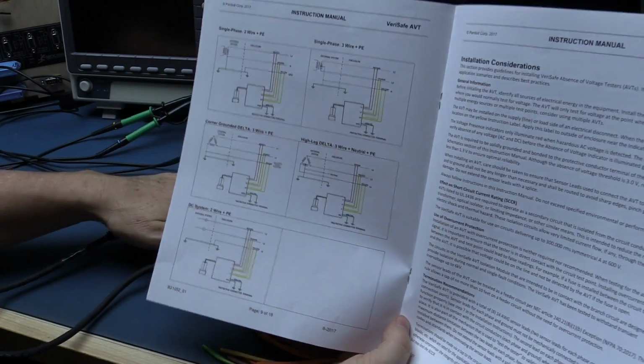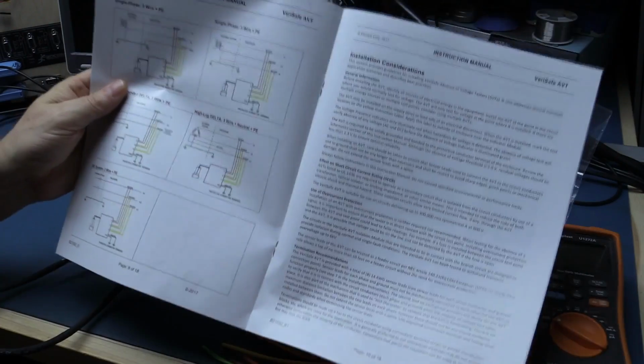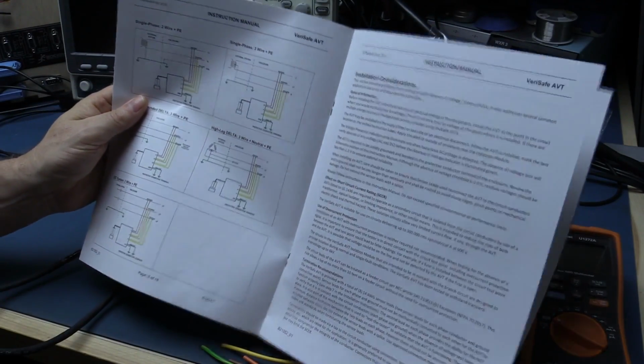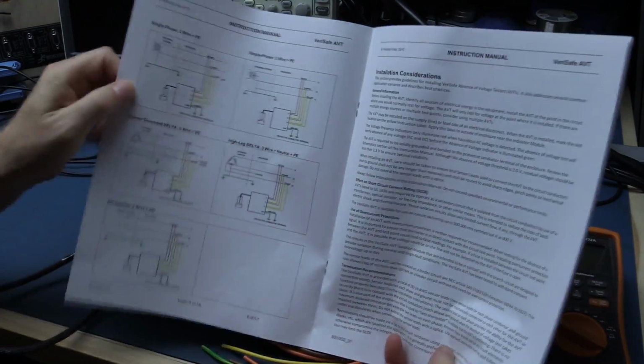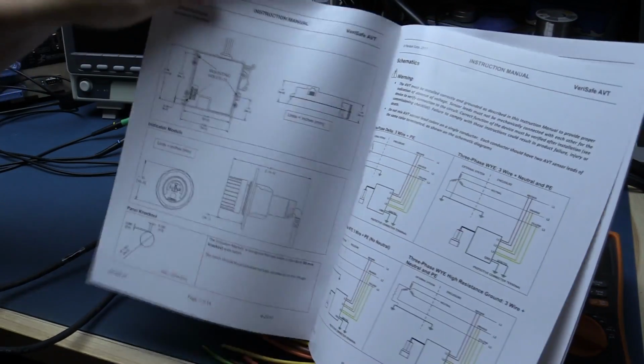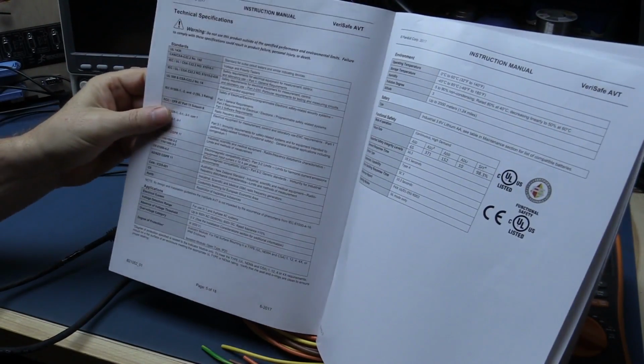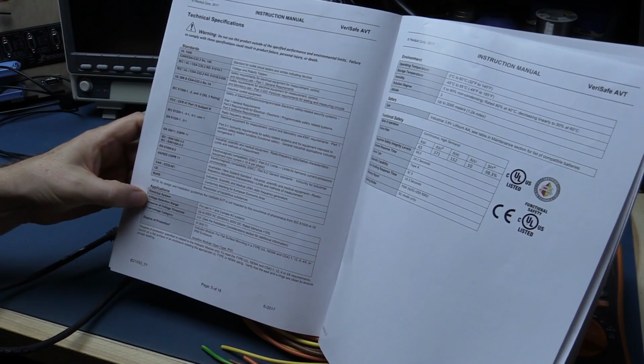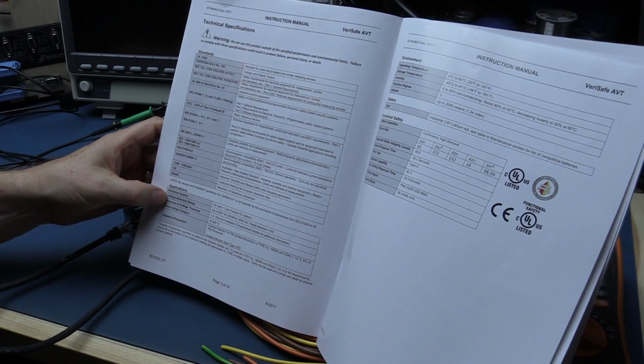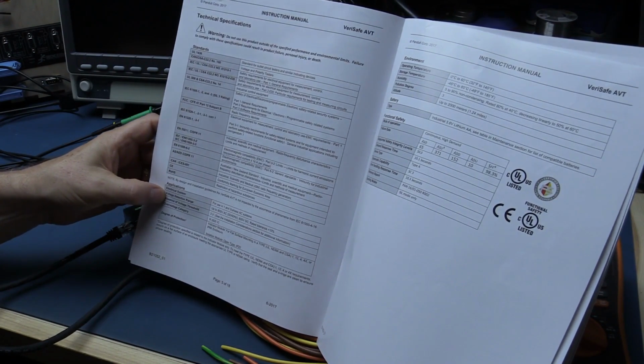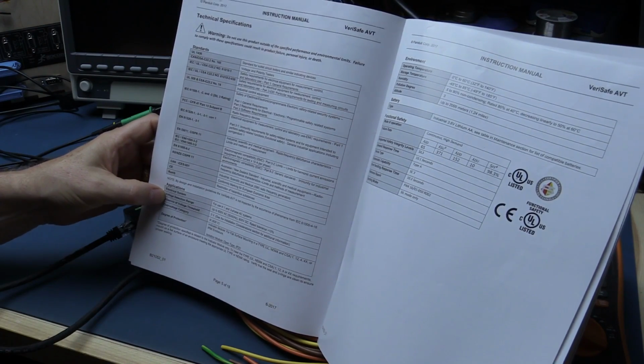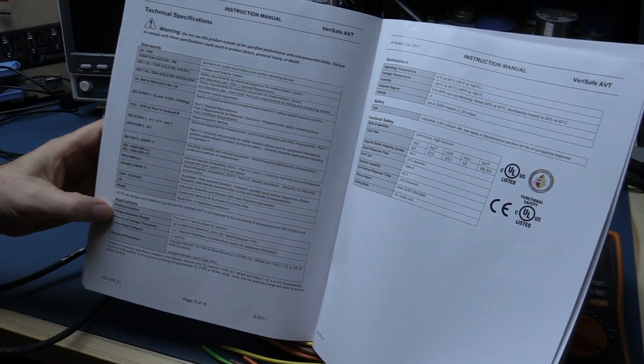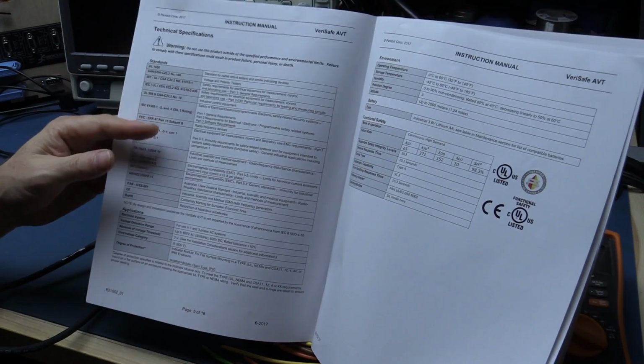So we'll do a little experimenting to see how low it will go before it says things are safe. It does tell us how low it's supposed to go. Absence of voltage threshold is 3 volts, so anything below 3 it determines is safe. Anything above 3 volts should start showing up as a red light indicating it's not off.